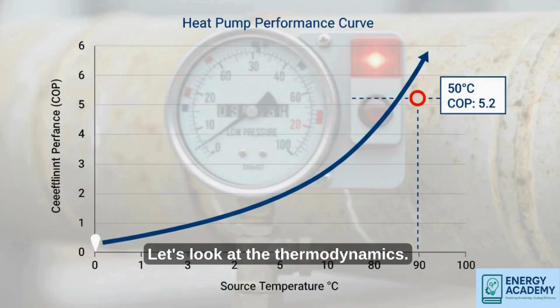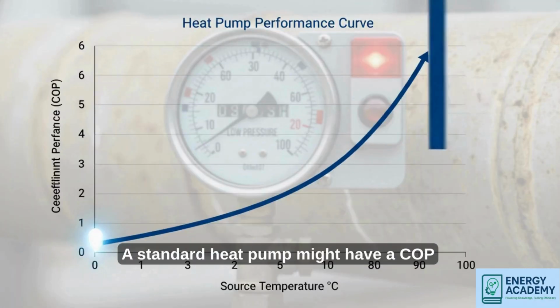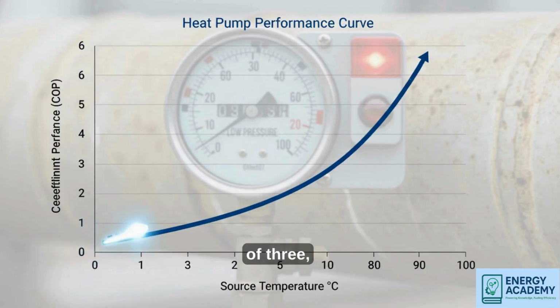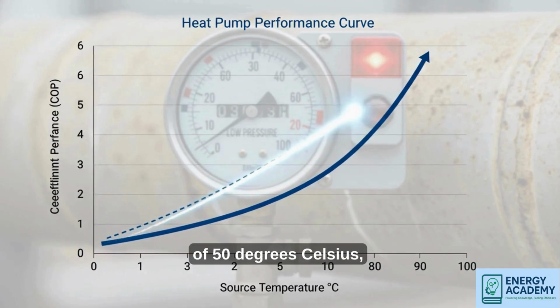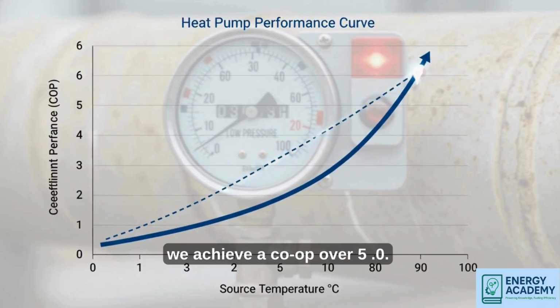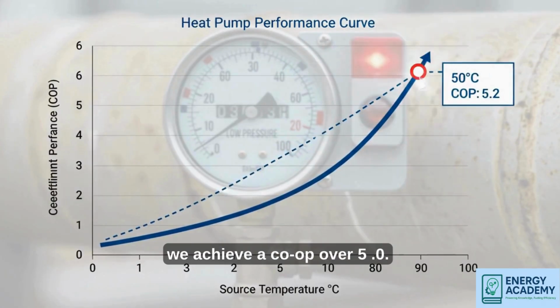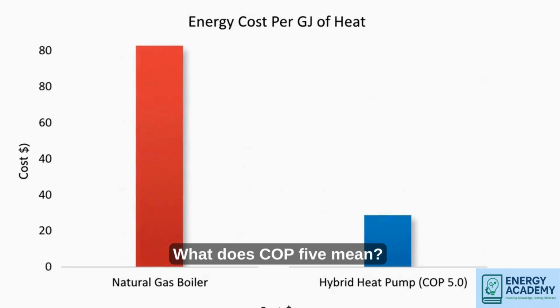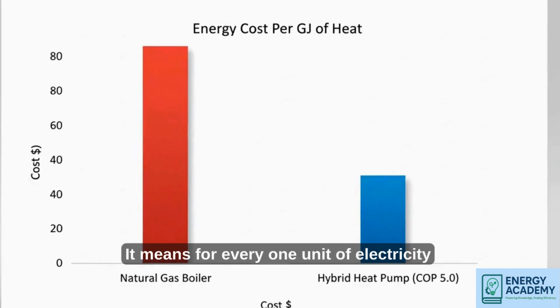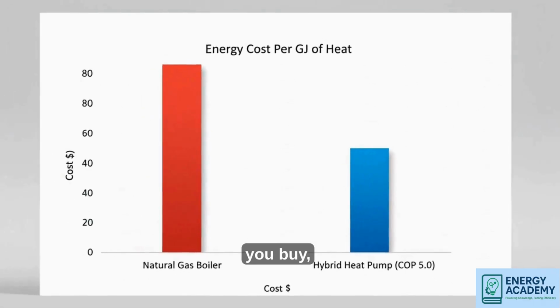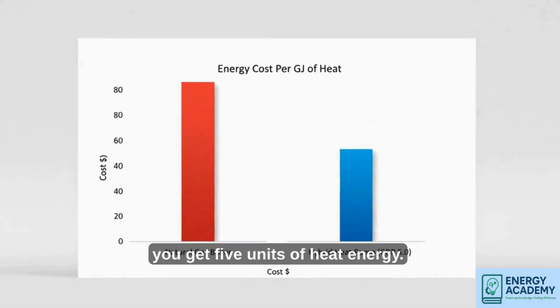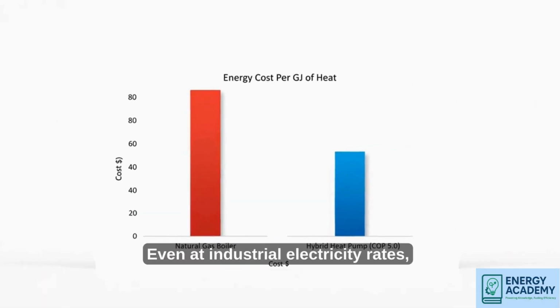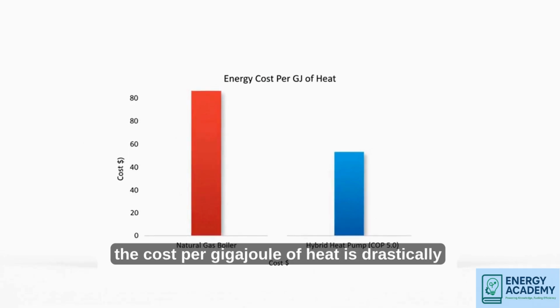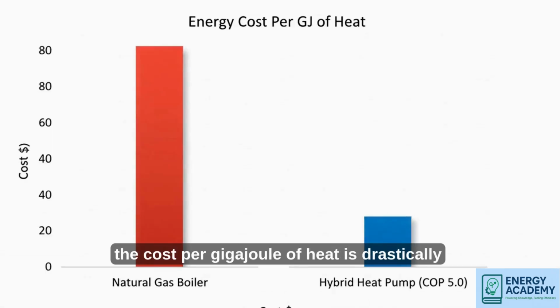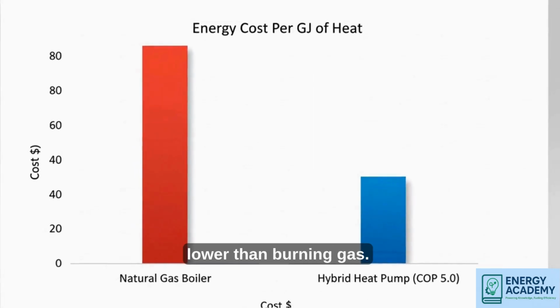Let's look at the thermodynamics. A standard heat pump might have a COP of 3, but by using a hybrid solar waste source of 50 degrees Celsius, we achieve a COP over 5.0. What does COP 5 mean? It means for every 1 unit of electricity you buy, you get 5 units of heat energy. Even at industrial electricity rates, the cost per gigajoule of heat is drastically lower than burning gas.